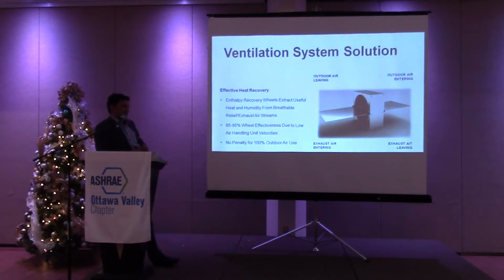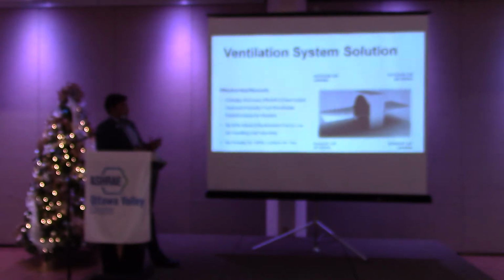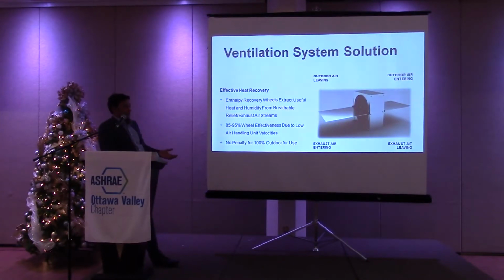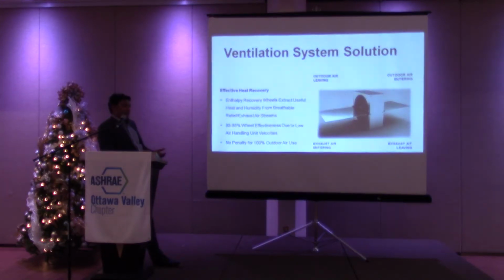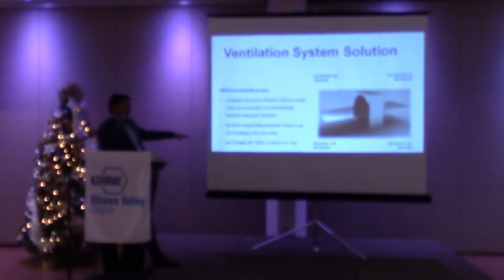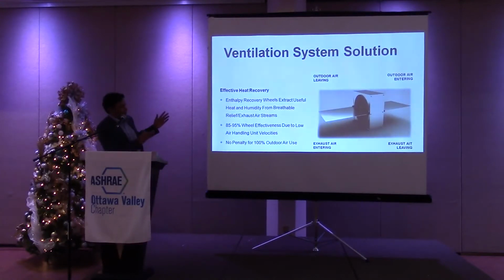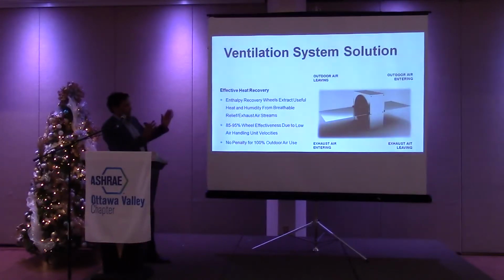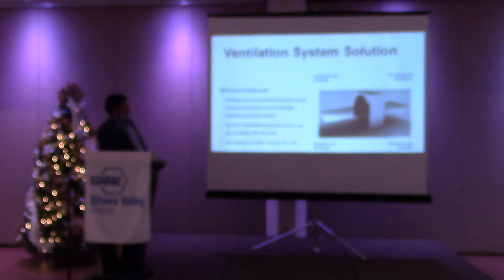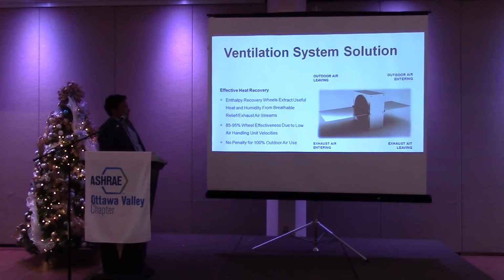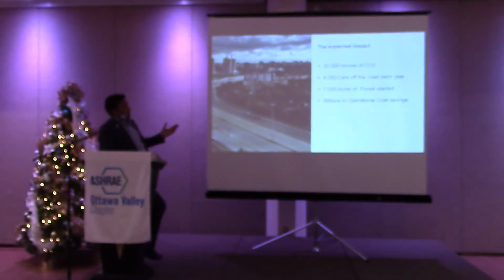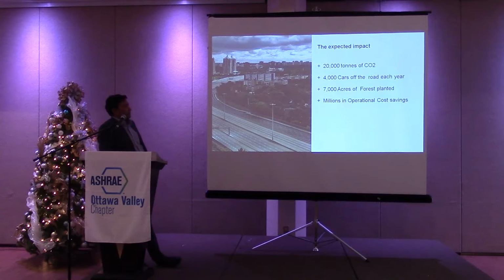And because CSA requires traditionally only 33% outside air, and you're recovering 85 to 95% of that energy, we found there was no penalty for 100% outdoor air handling. I mean, you pay for it in cost, but there was no energy penalty in this case. And so, we tried to reduce fan energy, oversized the air handlers, side benefit, effectiveness goes up, and we don't pay the penalty. So that was definitely a big win and an aha moment on the project. So the end result, 20,000 tons of CO2 being reduced, 4,000 cars off the road, and millions in operational savings.